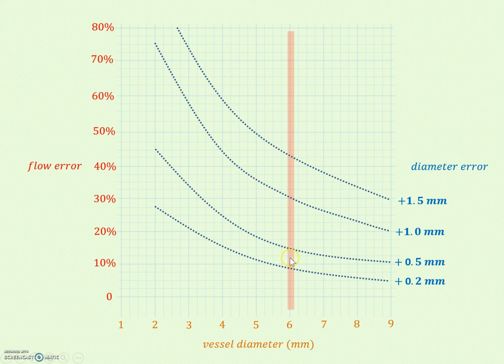And so if you're doing something like a brachial artery, which is even smaller, the error is magnified. So these kinds of measurement errors are well within reason. Even if you're the best sonographer in the world, some of these are at the limit of the measurement error of the device itself. So it calls into question using really accurate changes in flow in smaller vessels in the periphery.